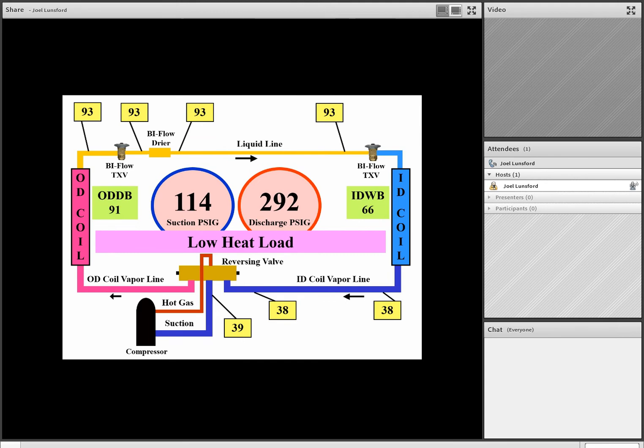Okay, team, at this time, let's take a look at this service call. It's a 410A service call. I'd like everybody to take a real good look. We see that we've got low suction pressure. And please notice all the temperature probes around the refrigeration circuit. Look at those closely.